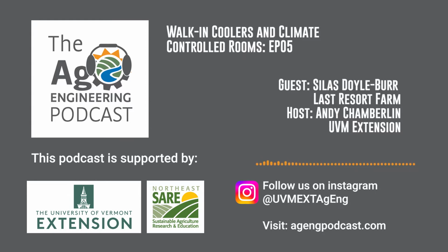And he's actually, Chris Callahan, I think, his technology for what he calls the DoRight sensors. These sensors can measure temperature and relative humidity. Kind of groundbreaking technology, right? Yeah. A little bit about the DoRight is it's a humidity sensor that has really good accuracy at really low temperatures and really high humidities. There are a lot of humidity sensors out there, but their range of accuracy goes out to lunch, A, when it gets really high humidity, and B, when it gets really cold, which is a cooler environment.